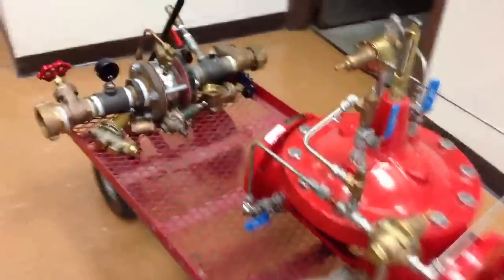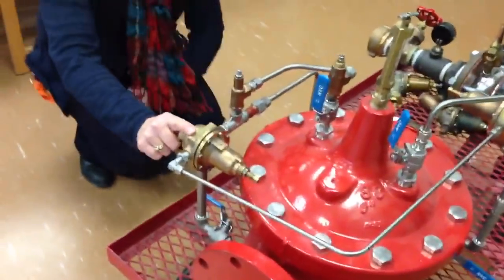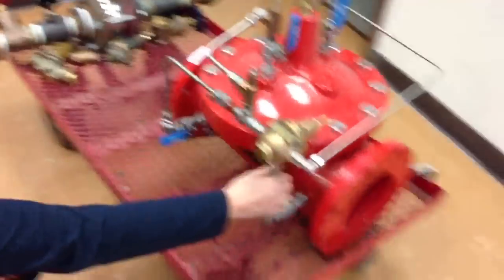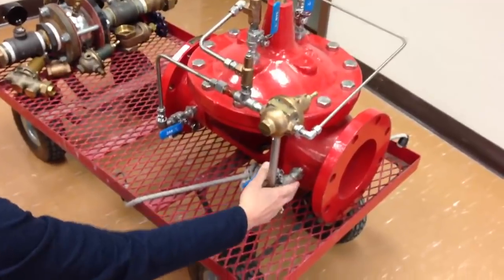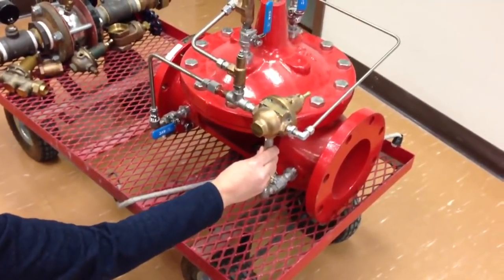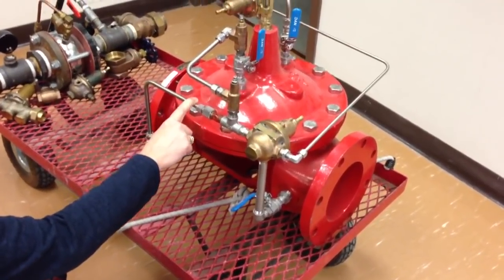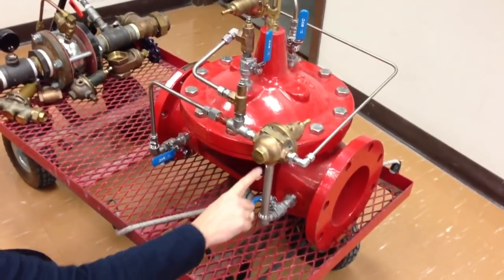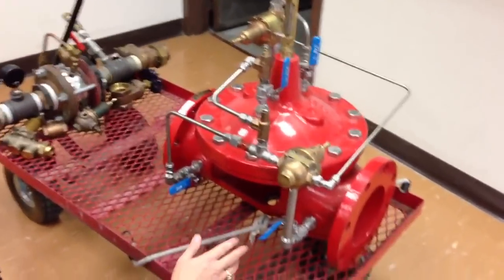From the back side, from high pressure, low pressure. And also you can tell by the piping. Your CRD in this application is always going to have a larger pipe leading to the downstream side, the lower pressure side, because it needs to be able to take off more water than this can put on. So that's another indicator of which is upstream and which is downstream.